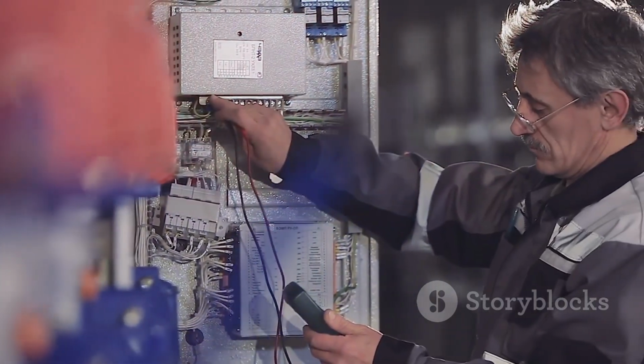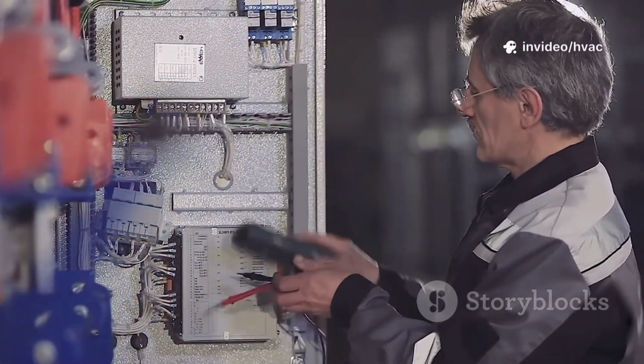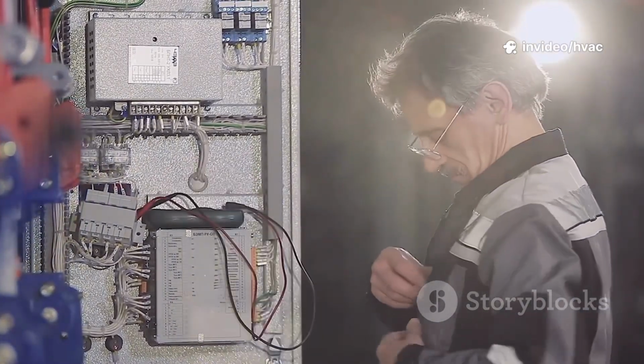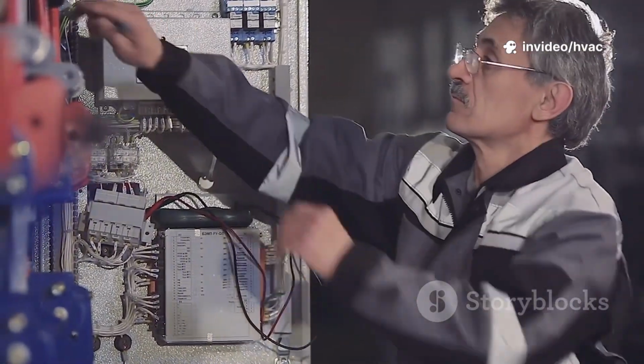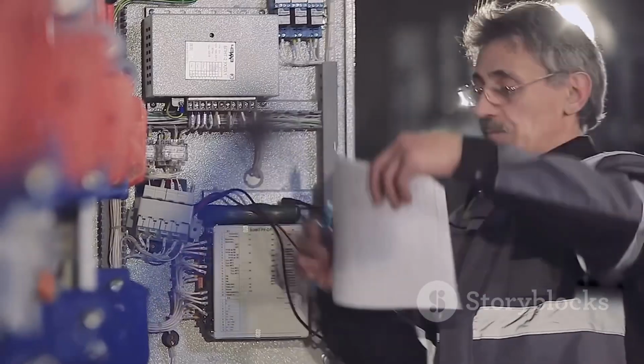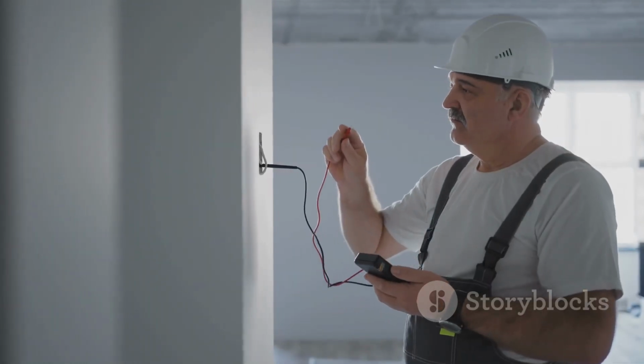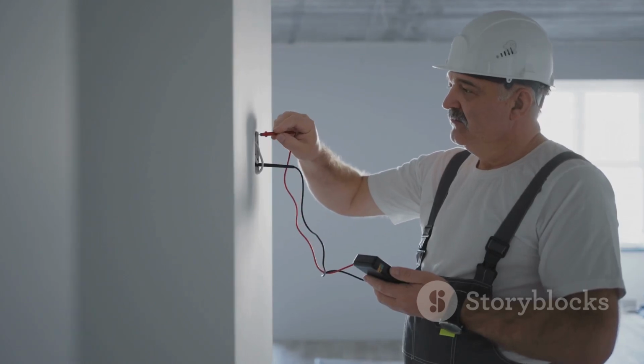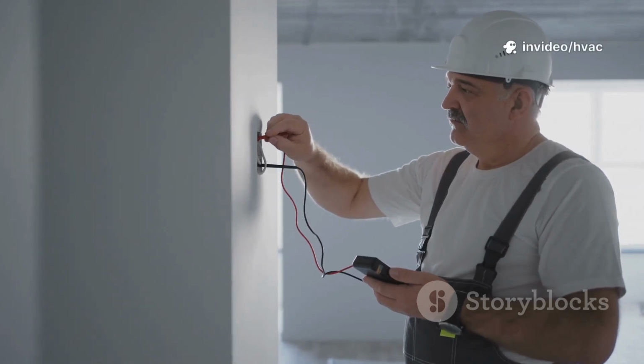Now let's get specific for design engineers. For condenser water cooling towers, safety interlocks are critical. The basin low-level switch should be NC, closed when water is at a safe level, opening if water drops too low to stop the tower and protect the pump. The fan motor overload is also NC, opening on fault to break the circuit.